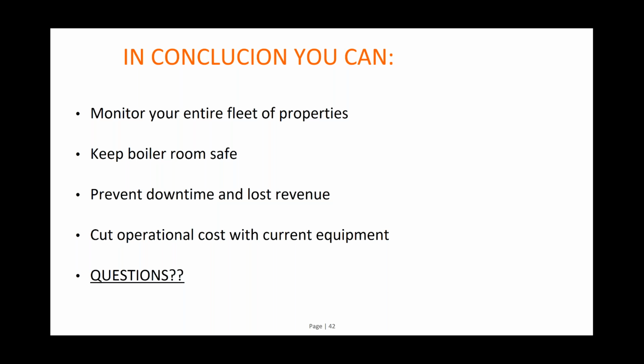And the way we are able to do it is not upon failure. We are able to detect and forecast when things would happen. In the case of the electrode, if we observe conditions where the unit is behaving in a certain way, mostly during the day and depending on temperatures, we would recommend that you inspect the electrode even before it is warped. Or maybe it has started to warp, but it hasn't gotten to the stage where your unit would be completely shut down. So all the typical conditions you see in a boiler room is what we're working on today.